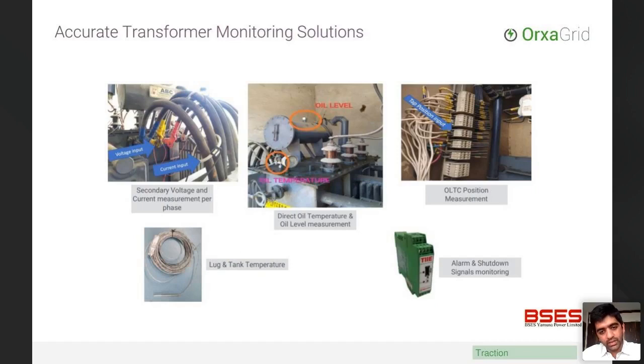By installing surface temperature sensors, we reduce the cost of installation drastically. We reduce the outage time required on these critical transformers drastically, and we provide the same accuracy for the results. So if you are interested in only temperature monitoring to understand the hotspot temperatures on your secondary transformers, which have not been monitored historically because of cost factors, by implementing our temperature algorithm we can do this at a very economical cost. This white paper is available on our website, and I would love to share it with anyone who is interested.